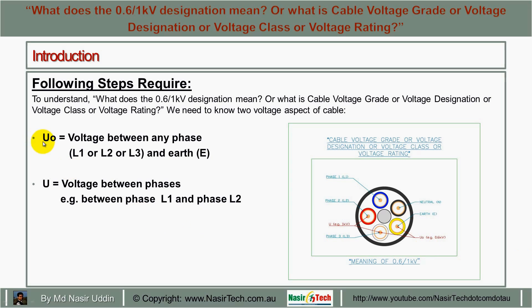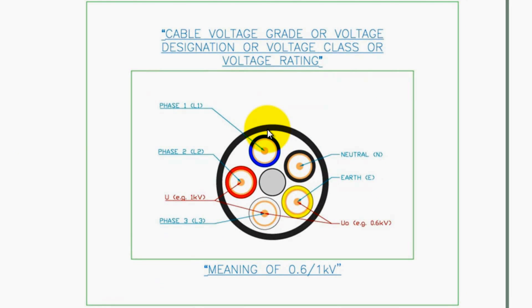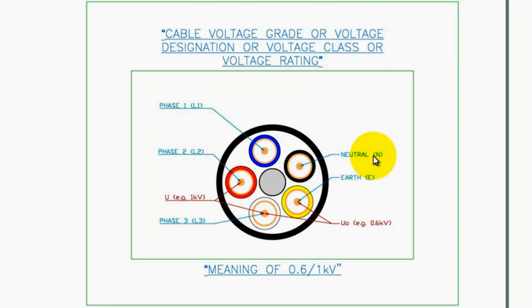One is U0. U0 means the voltage between any phase and earth. In this picture I am showing a 4-core plus earth cable. We have phase 1 or line 1, phase 2 or line 2, phase 3 or line 3, a neutral core, and an earth core. U0 means the voltage difference between any phase and the earth core.